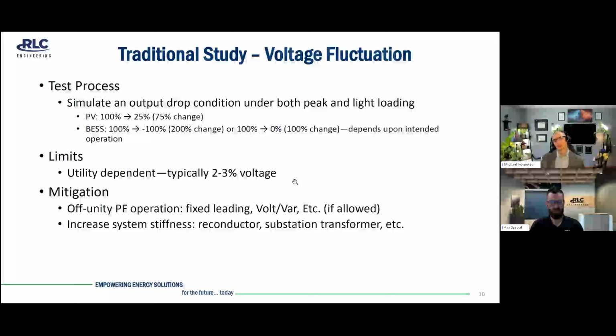For voltage fluctuation, these are where output drop tests tend to come into play. For PV, we typically use a 75% output drop, simulating cloud shading. For battery energy storage, it really depends what you're going to be looking at, and it depends on how that battery is going to be operated. You might look at the conservative scenario of 100% discharge to 100% charging. So that's a 200% change in output for that battery. Or we might look at just the transition from 100% discharge to 0, or 0% to 100% discharge.